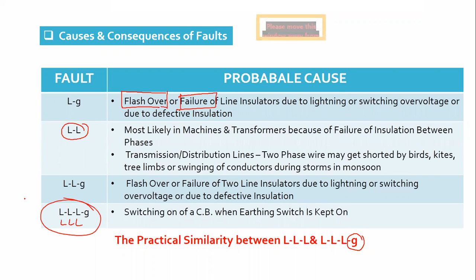And then we have seen the possibility of a triple line or triple line to ground fault, which is a very rare fault. Failure of interlocking between the circuit breaker and earth switch may lead to the triple line fault. However, as discussed, even though there is a triple line or triple line to ground fault, no current flows through the ground generally because it is a symmetrical fault, and that is why the ground current will be zero in case of triple line to ground fault. So electrically both the faults are similar. If I say triple line or triple line to ground, they do not carry any current to the ground.